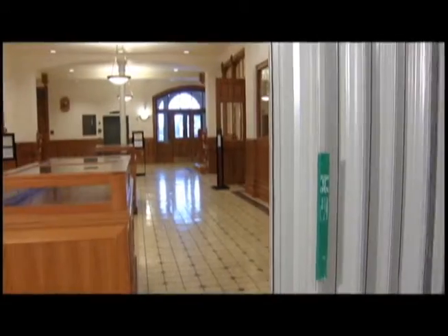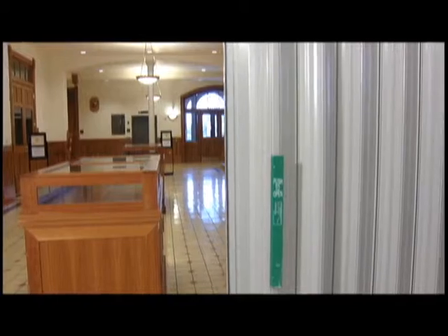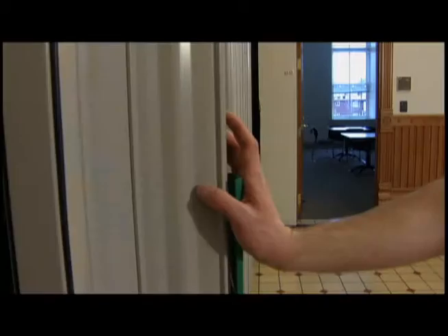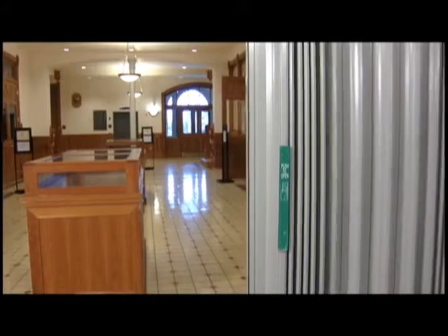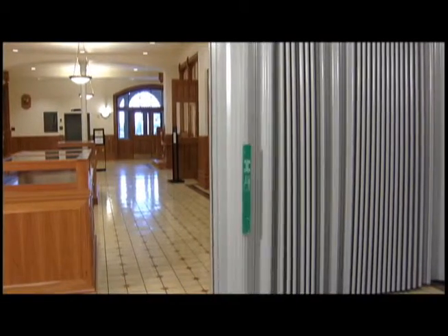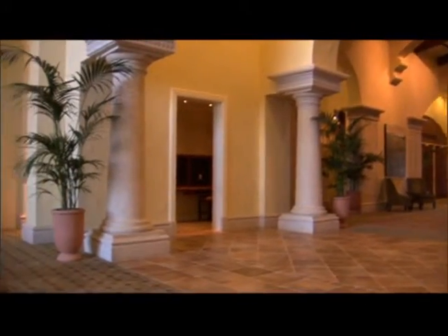The One Door FireGuard system is equipped with specially designed fire exit type hardware. This push panel is readily identifiable and responds to only 3 to 4 pounds of pressure. The door will open a preset distance, then pause, allowing building occupants to exit the space, and then the door will automatically reclose. The opening width of the door is flexible and can be programmed to any opening distance.